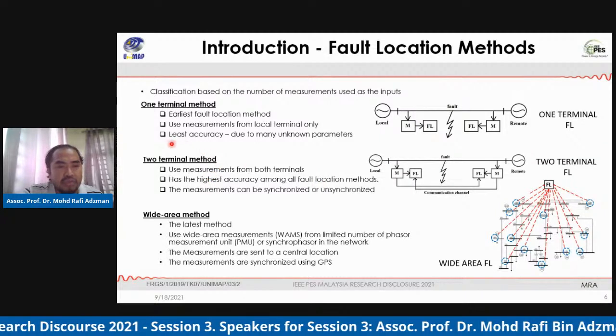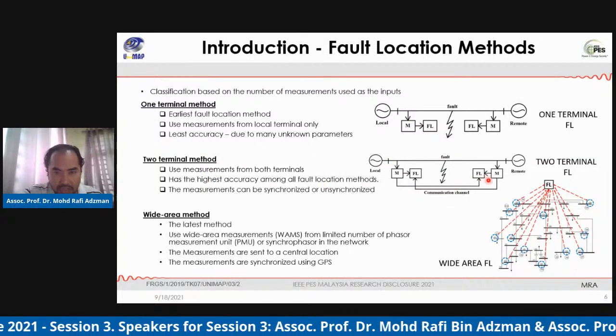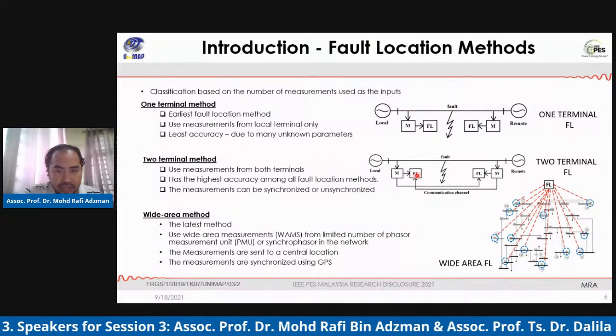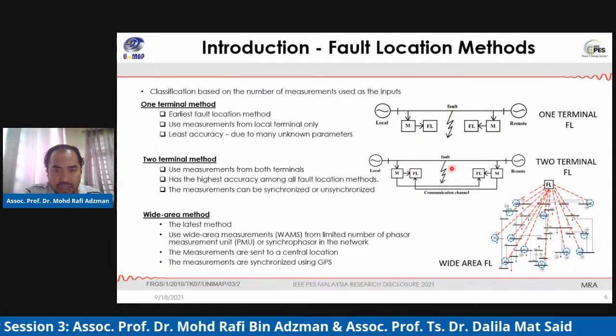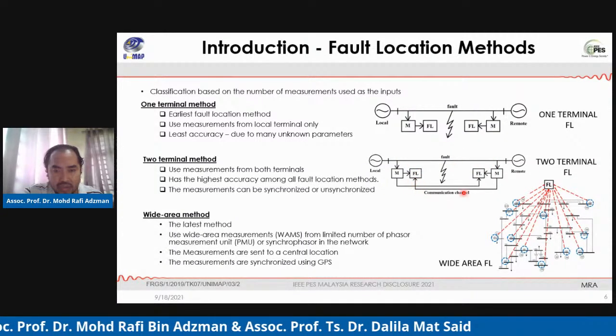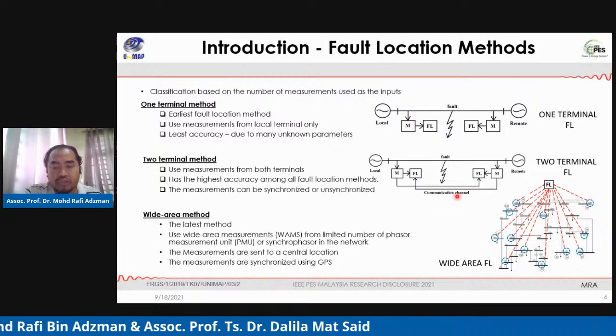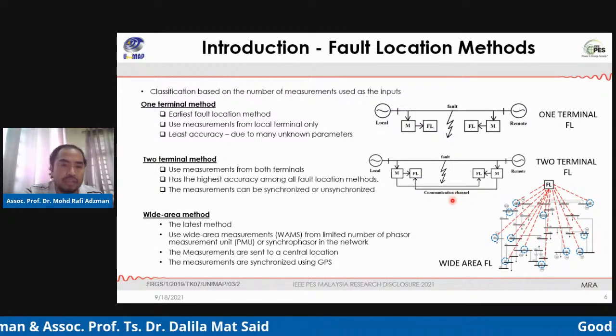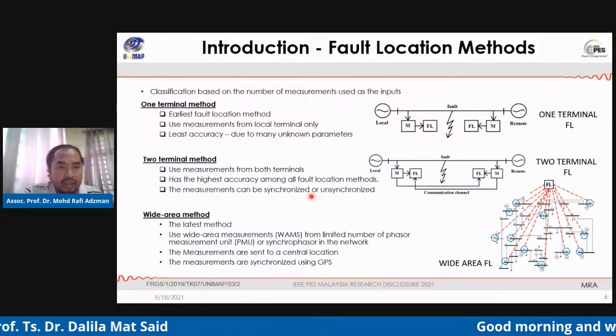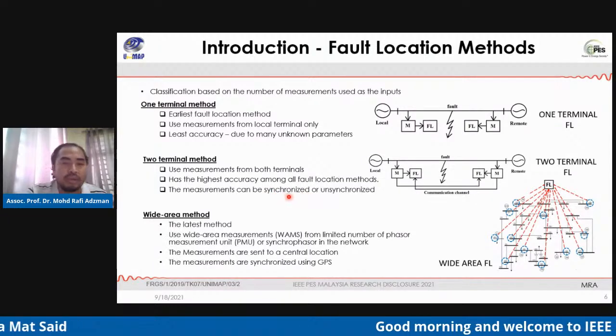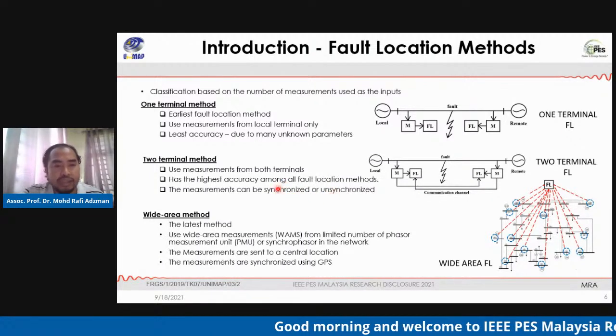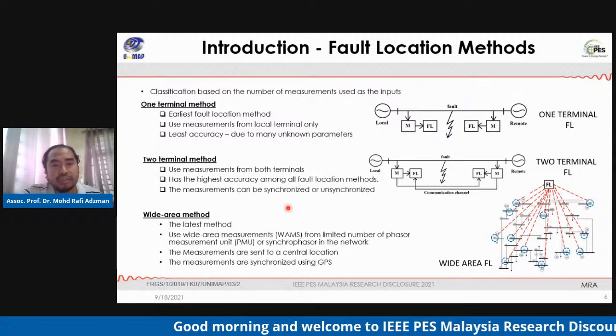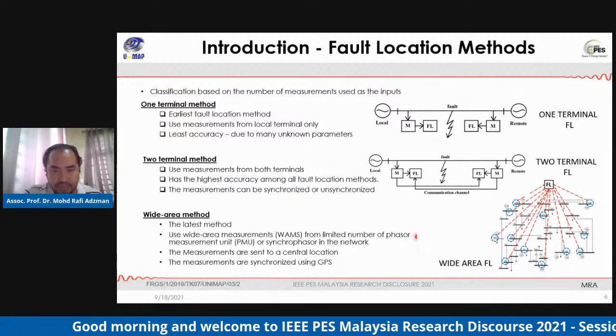Next, we have the two terminal method. The measurement is done at these two terminals, and the two terminals can communicate through fiber optic, for example. It has the highest accuracy among all fault location methods, and the measurement can be synchronized or unsynchronized.